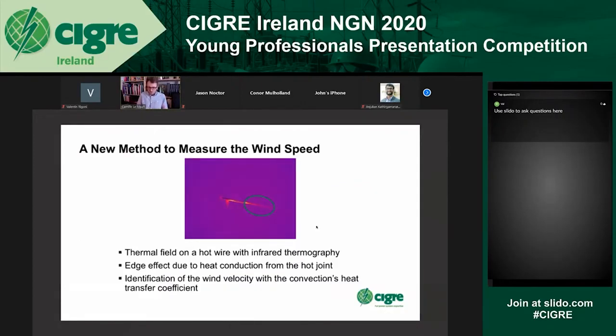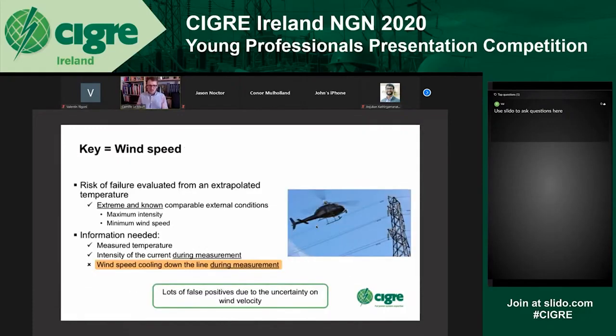We want the resistance of the joint because this doesn't change when we change the external conditions. But to do so, we need the temperature of the joint, and we have it with the infrared camera—we can measure it. We also need the intensity of the current flowing inside the joint at the moment we do the infrared measurement, and we have it from the current transformers at the surrounding substation.